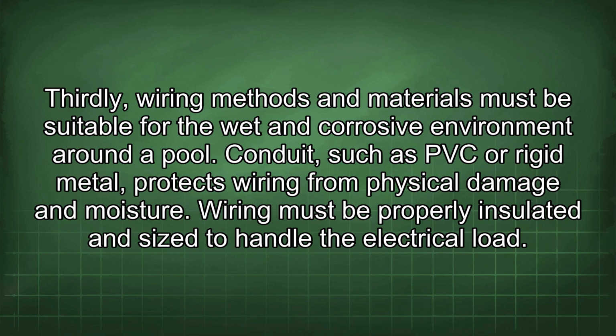Thirdly, wiring methods and materials must be suitable for the wet and corrosive environment around a pool. Conduit, such as PVC or rigid metal, protects wiring from physical damage and moisture. Wiring must be properly insulated and sized to handle the electrical load.